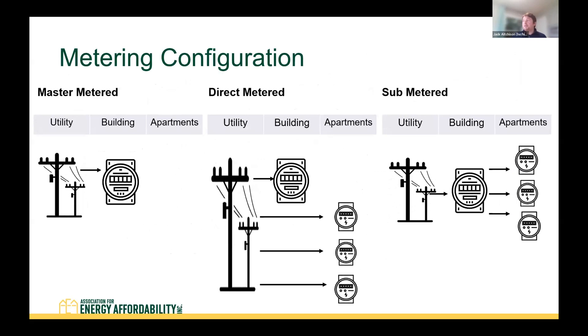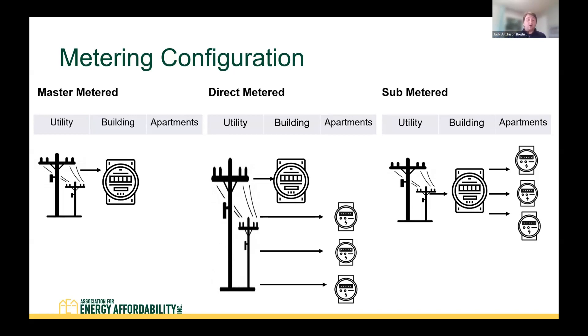A lot of the variety in multifamily electrical infrastructure is directly related to metering type. We have three standard metering types: master metered, which is most like a single family home with a clear delineation between utility and owner equipment; direct metered, the most typical multifamily setup shown in the previous slide; and sub metered, a hybrid with a main disconnect plus separate sub meters for different end uses or dwelling units. Within these types, we also have variation based on building size, number of buildings, and year the property was built.